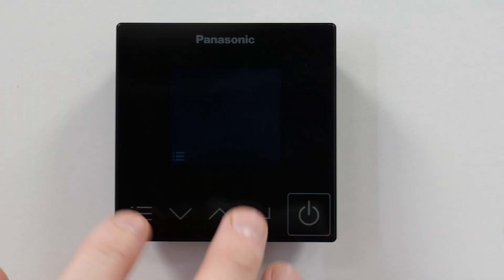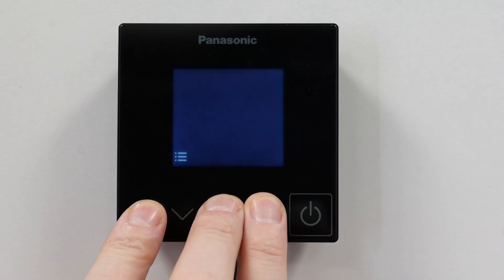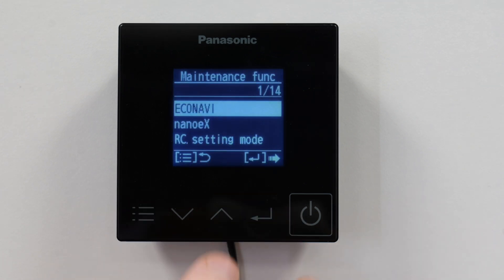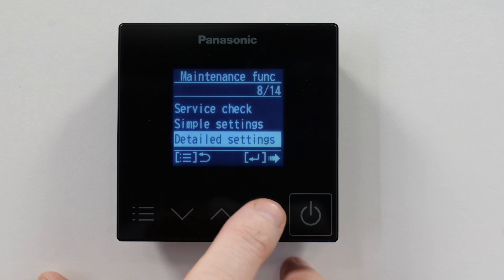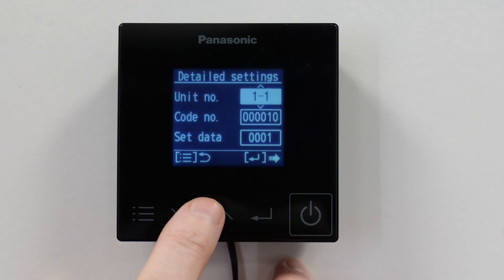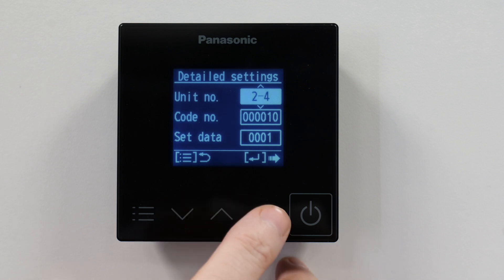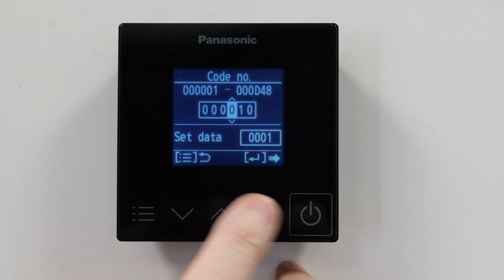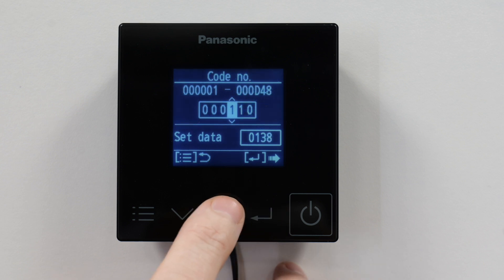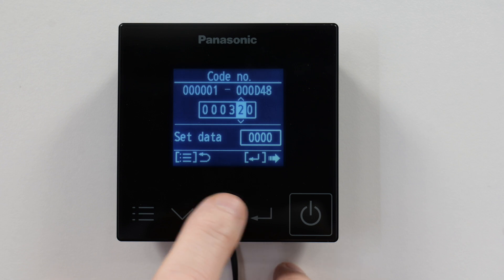To set up for low temperature, you're going to need to press three buttons — menu, up arrow, and enter — for four seconds. Once you're in there, go down to detailed settings. The first thing we need to do is change the mismatch setting for the unit so we can get it to run. At this point you press the code number and then press and hold enter for five seconds.